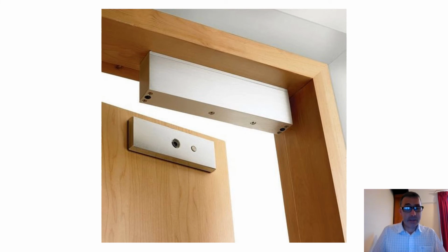That's an example of a magnetic lock on a door. So again, these can be linked to the laser so that when the laser is fired up, the doors are automatically locked. A safety system could be in place, so break glass to enter the controlled area if you need to do so in an emergency. For example, there's a cardiac arrest in the room, so the cardiac team can get in quickly. Not everybody uses these, but it's a nice system to use to prevent people from coming in.